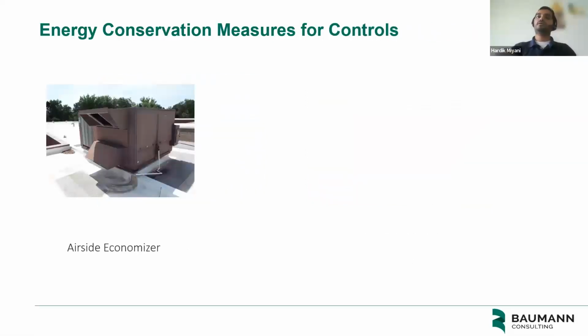Next is focusing on the ECMs for the controls, that is the air side economizer. Usually what we see is the building uses chillers and compressors for providing cooling into the building. But whenever the ambient temperature is less than the return air temperature, you can take advantage of bringing in outside cold air into the building for cooling. In other words, this is also known as a free cooling strategy as part of retro commissioning.